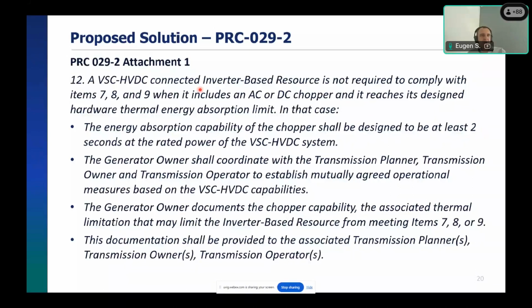It was not intended by the drafting team, but the impression was raised that VSC HVDC systems don't need to be compliant with the requirements given in items 7, 8, and 9. That was not the case and was not the intention of the drafting team. So the drafting team came up with a new definition, saying yes, VSC HVDC systems utilizing AC or DC choppers also need to comply with requirements 7, 8, and 9, but only up to the capability of the choppers installed.